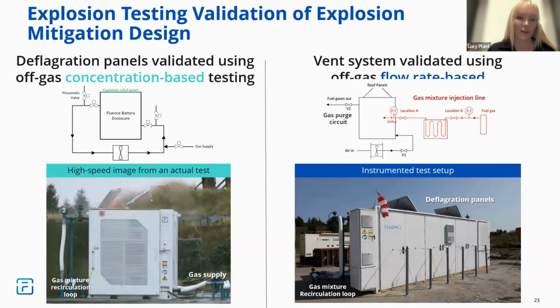We want to know, do they work correctly? Do they come off correctly? Does it work in releasing the panels? What you want is that they're the weakest point within the battery. You don't want the doors blowing off the front and potentially impacting a cell opposite it, or worse, potentially hitting a first responder who's close by monitoring that system. So we want to make sure that is working correctly, that they're coming off.